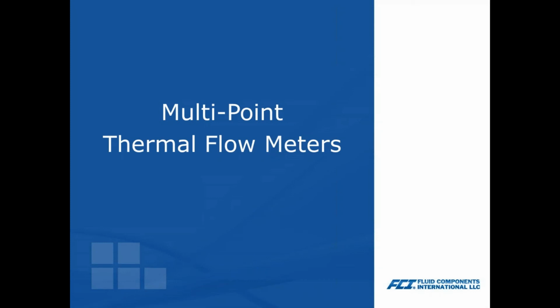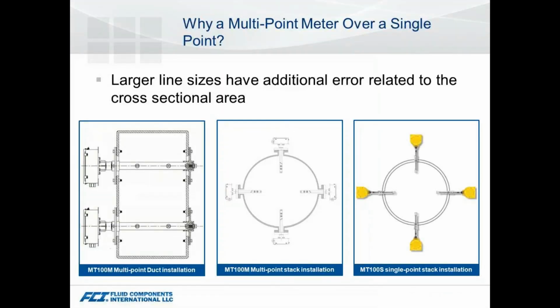All right. The next part of the FCI family is multi-point thermal flow meters, and I touched on it briefly, the need for a multi-point. When we get into larger ducts, larger lines, 20 inches or higher, a single point measurement in the center of that duct or pipe is going to lead to some inaccuracies. Now, in some areas, it might be only 1%, but as you get into the 30-inch range, you might be talking 5-6% error just by using that single point sensor. So at that point, what we want to do is look at it by breaking it down cross-sectionally and putting more points into the system, and then averaging all of those points into a single meter reading.